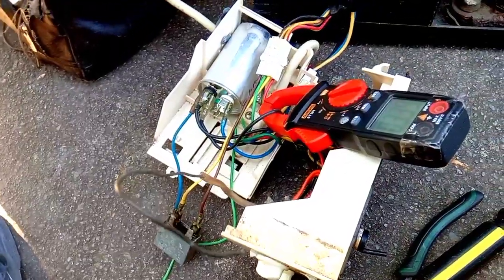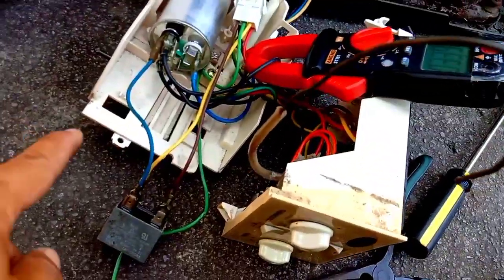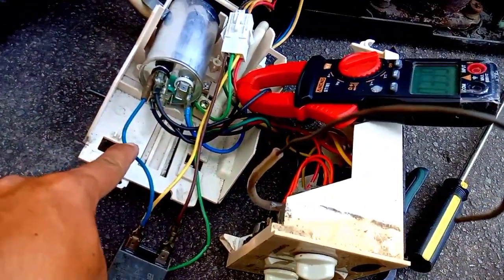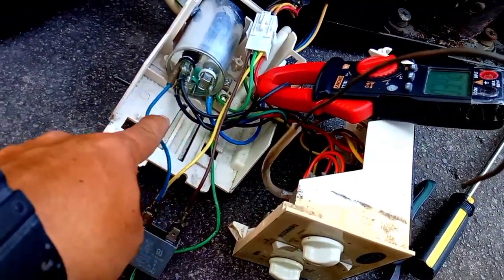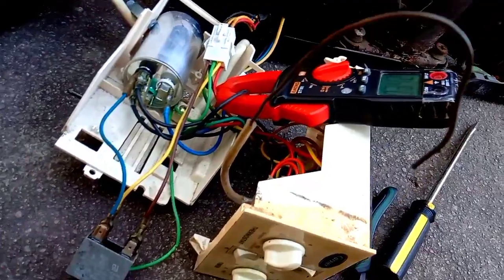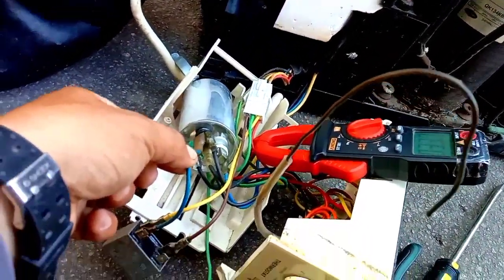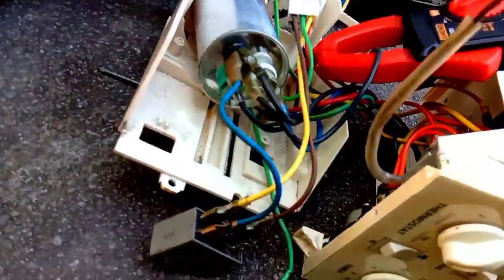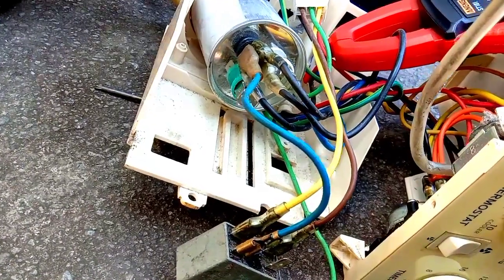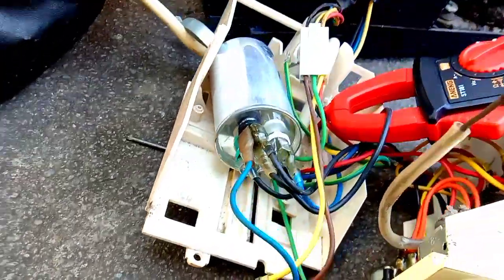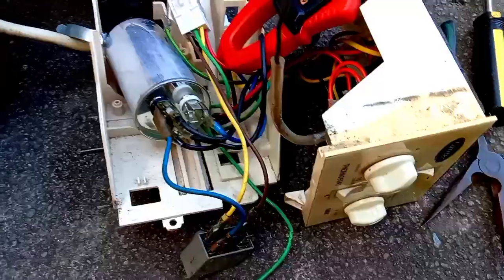We noticed that there is operation of the compressor, but the fan blade and the blower fan of the evaporator are not functioning. So we have declared only one defective part, that the fan capacitor maybe changed value in the dual type capacitor. So we have to condemn and change the fan capacitor.